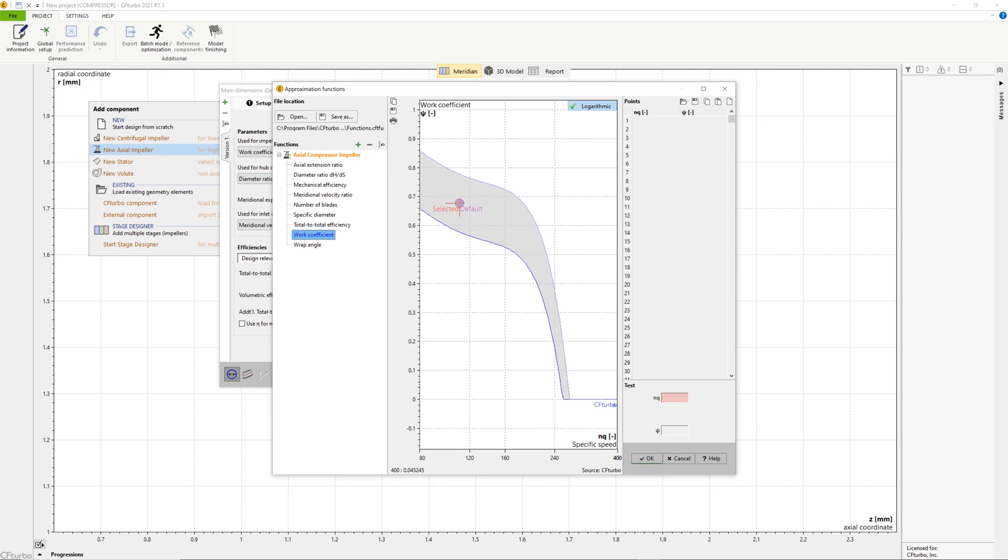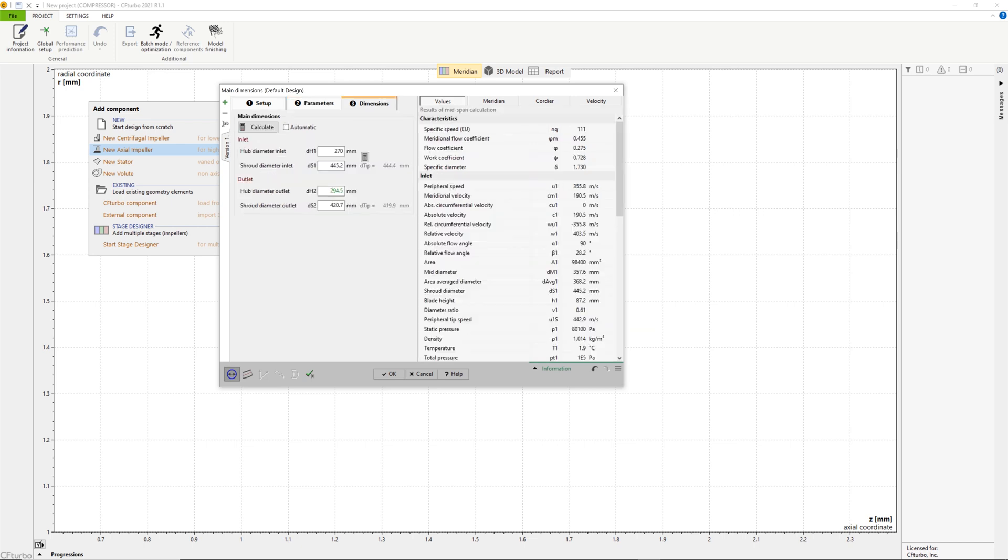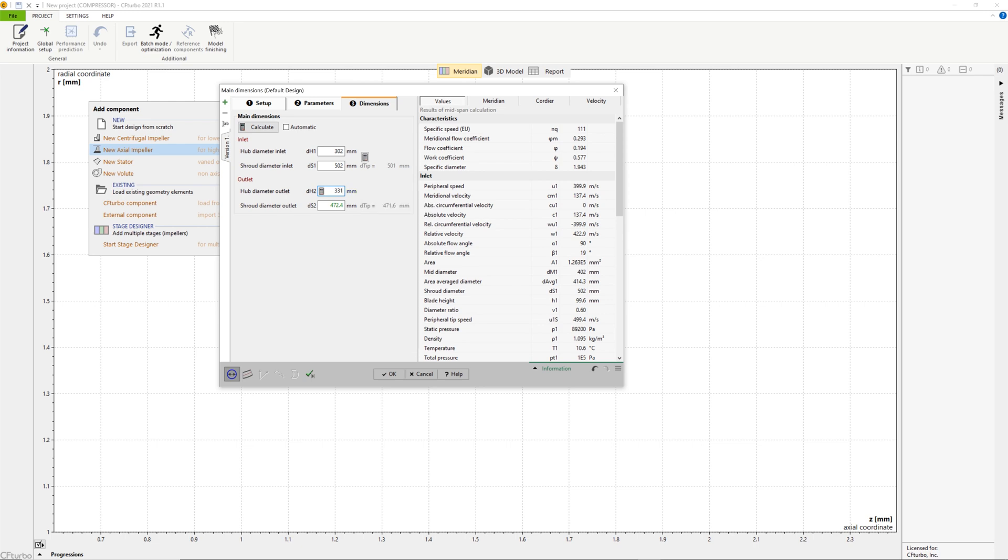To calculate the impeller main dimensions, CFTurbo uses numerous empirical correlations in the parameters section. In most cases, non-dimensional approximation functions are taken from textbooks, research papers, and our own data. Here we use the work coefficient to calculate the impeller diameter and a diameter ratio function to get the hub diameter. Additionally, several empirical efficiency correlations are implemented to get reasonable initial values of the impeller main dimensions.